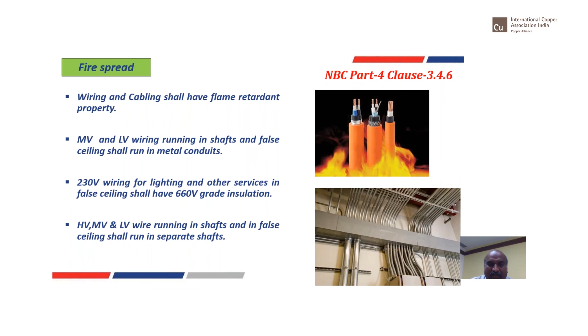So electrical distribution cable wiring shall be laid in a separate shaft. Yes, don't always have a single shaft in which you have cables, you have plumbing, you have all other devices going. The shaft shall be sealed at every floor. Yes, if there is a fire on the third floor, it should not spread to the second floor or first floor. Please ensure that proper sealing is done so that fire does not spread. All metallic sections shall be bonded, as we know, electrically, anywhere and everywhere as far as possible.